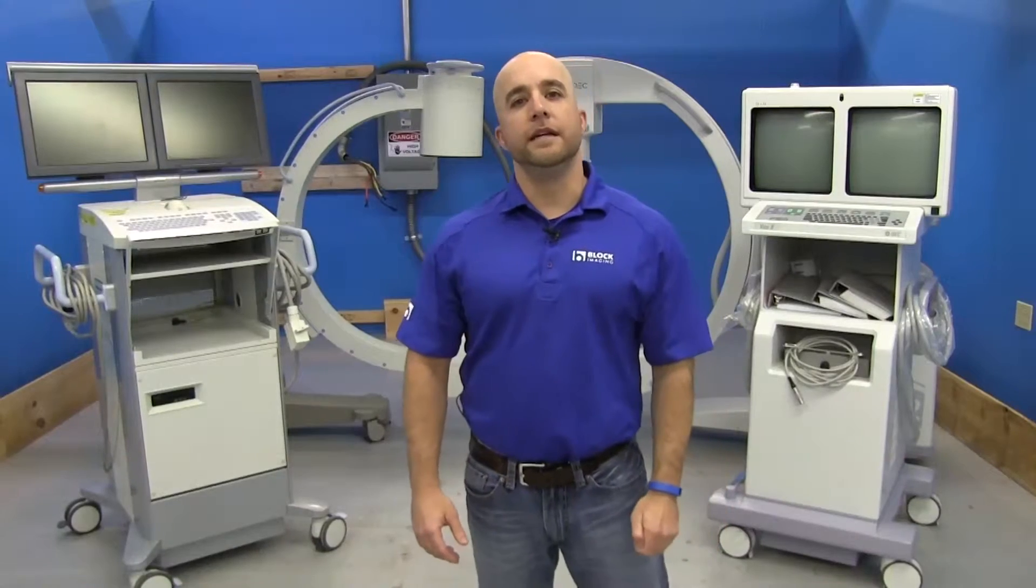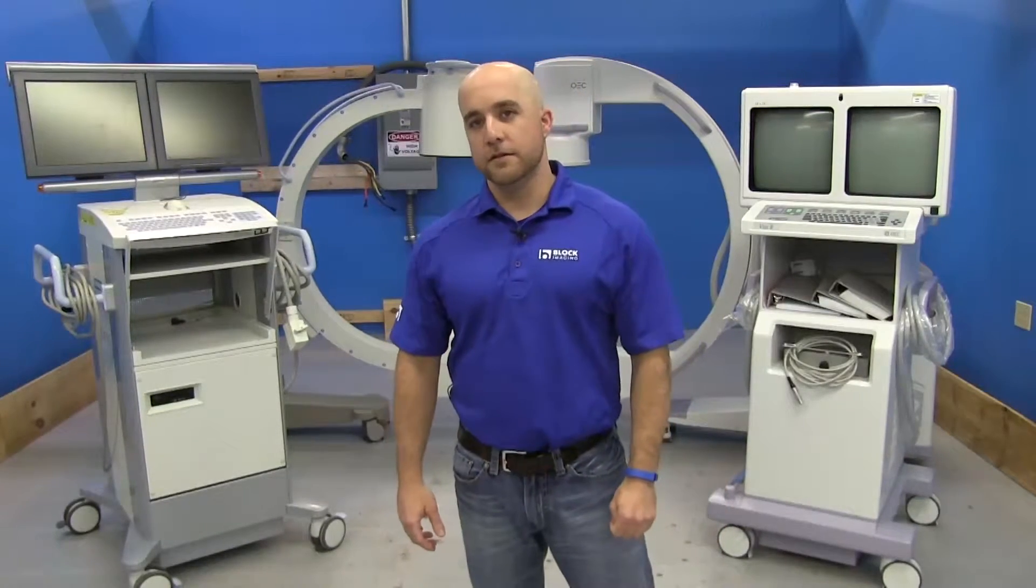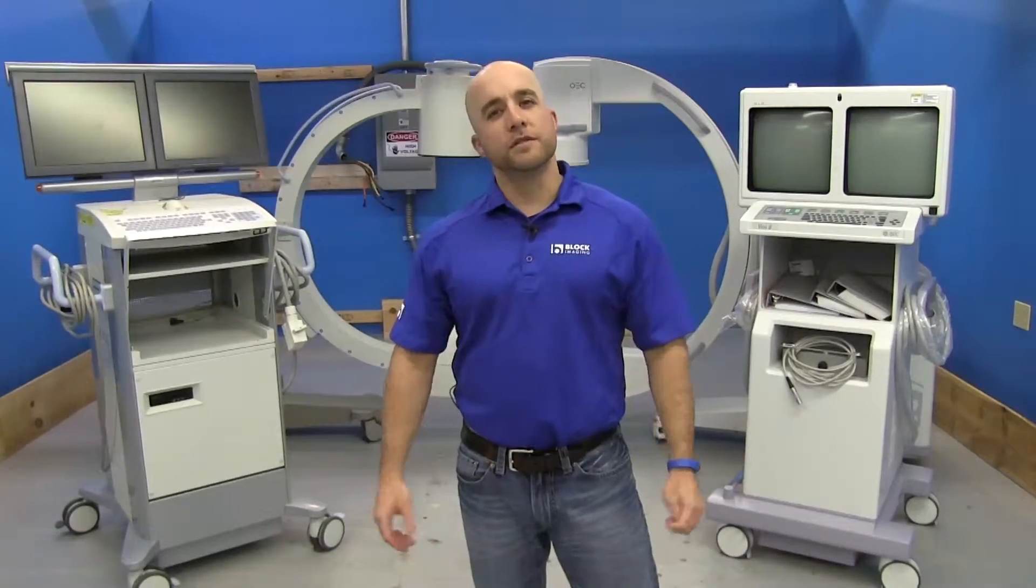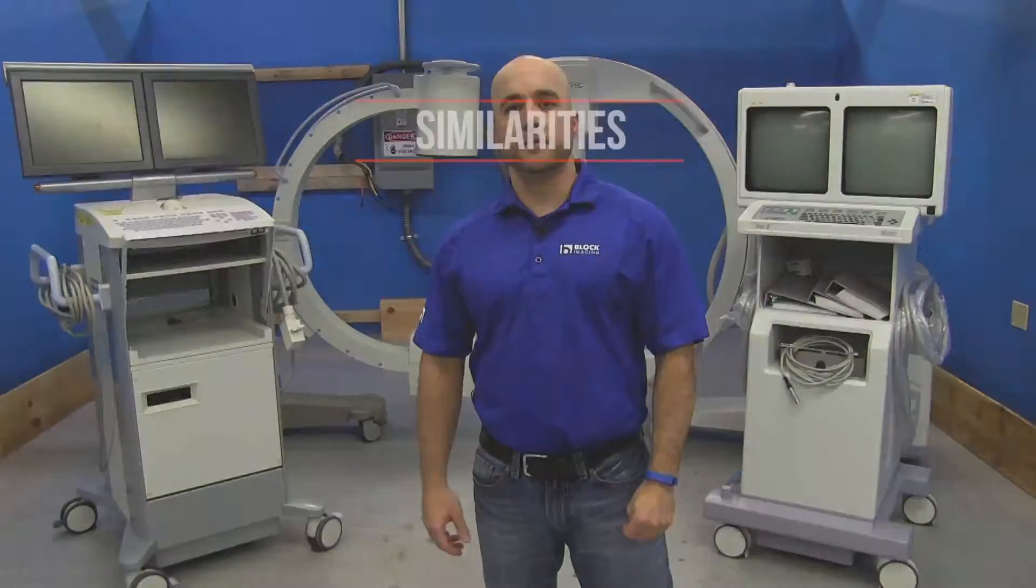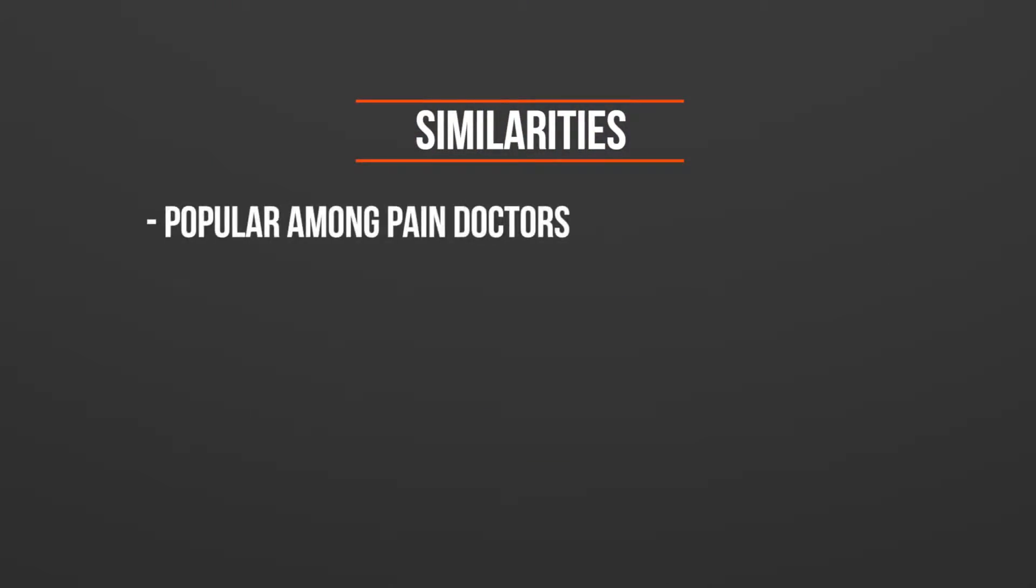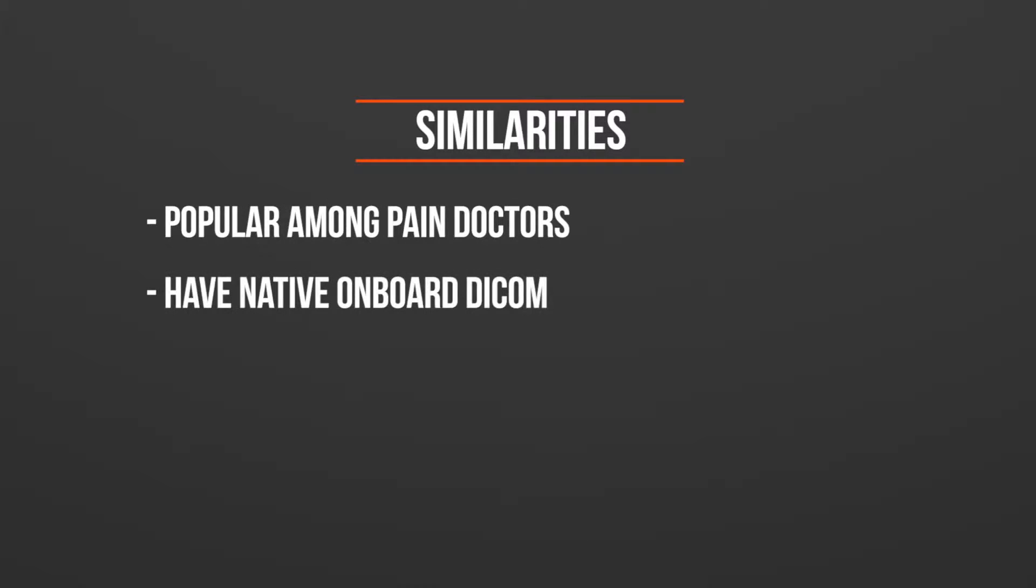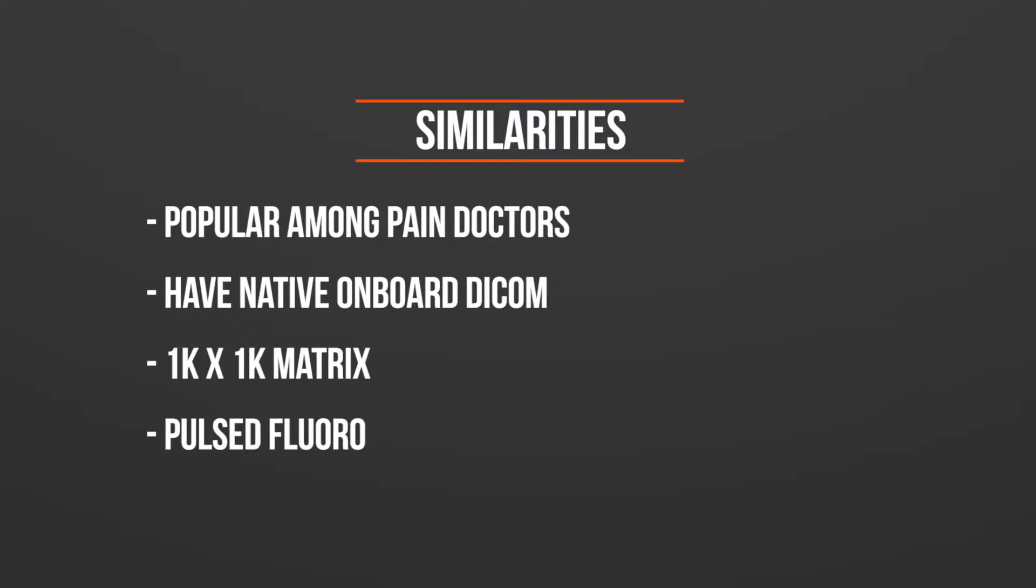Today we're going to be comparing the Siemens Arcadis Varic and the OEC 9800 C-arms. Let's start with some of the similarities. Both are extremely popular amongst pain docs and they both have native onboard DICOM. Both of them have the 1K by 1K imaging matrix and pulse fluoro.